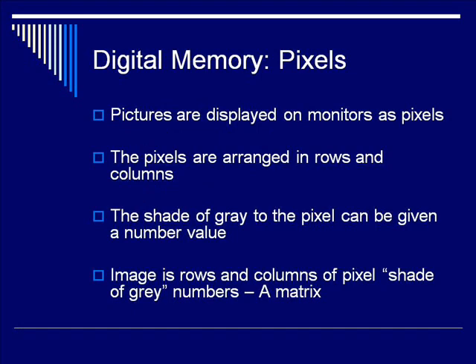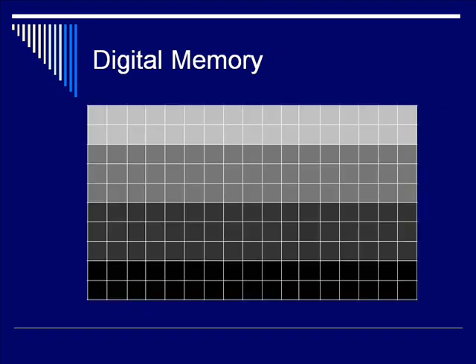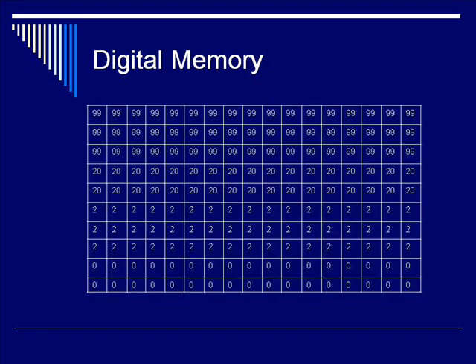This digitized signal is being stored in the scan converter, and we're slowly assembling an image. This image is displayed on the monitor and saved in memory as rows and columns of pixels — that's picture elements. We've already described how each pixel can be assigned a shade of gray as a number value. Now we're talking about rows and columns of numbers, which means the image is stored in the scan converter as a matrix.